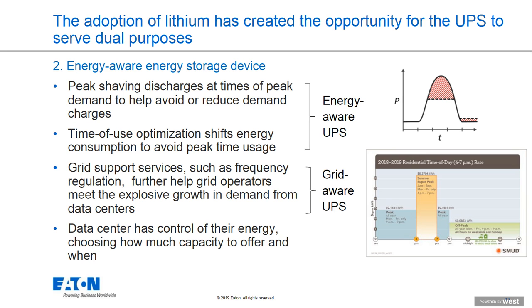The customer can always choose to enable or disable, but the utility company will provide a signal to the UPS controller that says, I need you to tweak your battery operation or to backfeed onto the grid, again, for short periods of time with a minimal amount of energy and in concert with other DERs in the geographical area to help with things like frequency control.